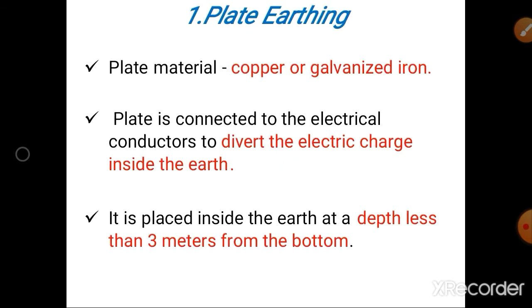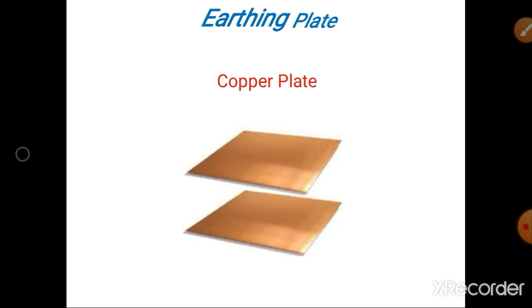The first one is plate earthing. In plate earthing, a plate like a copper plate or galvanized iron plate is buried inside the earth, and that plate is connected to the metal body of the appliances through the earth wire, so that the leakage current in the appliances is grounded to the earth through the copper plate. This is called plate earthing, and that plate is placed inside the earth at a depth less than 3 meters from the bottom. This is the important point. And see, this is the copper plate used for plate earthing.